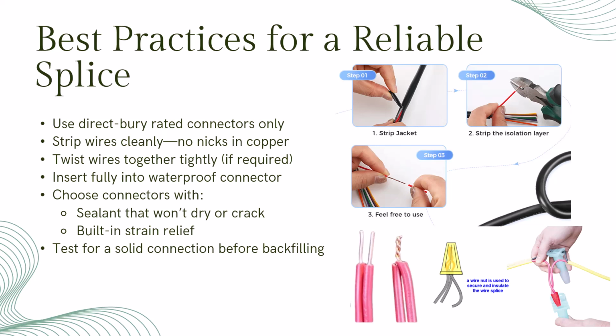These are the key steps. Use connectors designed for direct burial, no exceptions. Strip your wires carefully. You don't want to nick the copper because that weakens the conductor. If the connector requires it, twist the wires tight. Don't just jam them in. Insert them all the way into the connector and make sure the sealant surrounds the insulation, not just the copper. Look for connectors that provide a watertight seal and offer strain relief. This keeps the splice strong even with movement or moisture. And always give it a gentle tug to make sure it's solid before you bury it. A little extra care here goes a long way toward avoiding future failures underground.